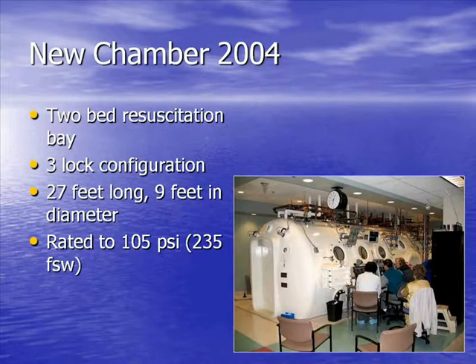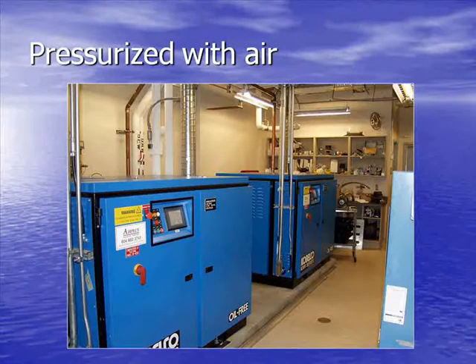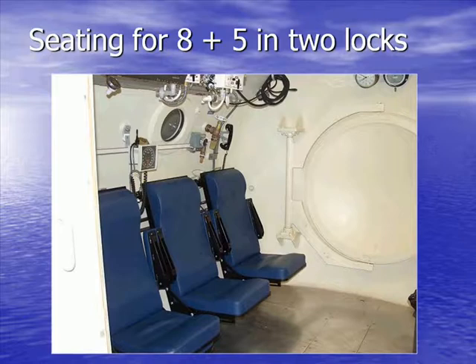There are actually two treatment locks. One is fully commissioned and being used. The second treatment lock is not fully commissioned but would not require much to commission it. The chamber is rated to 105 psi, which is 235 feet of seawater. Being a multi-place chamber, it's pressurized with air, not oxygen, using two large low-pressure oil-free compressors. The main treatment lock will seat eight persons — seven patients and one tender — and the smaller lock, which would be the research lock, has capacity for five.